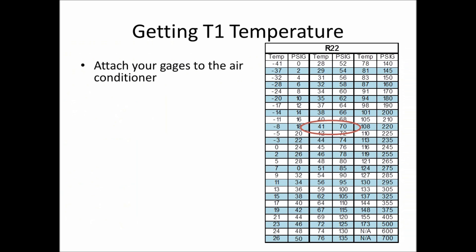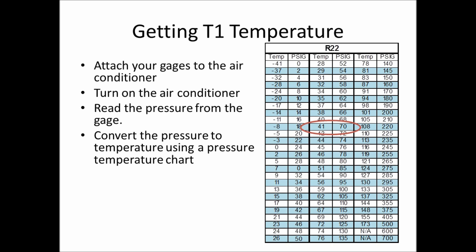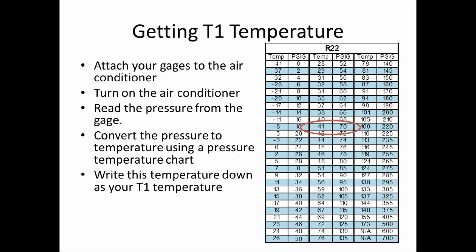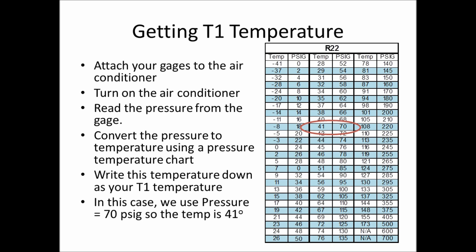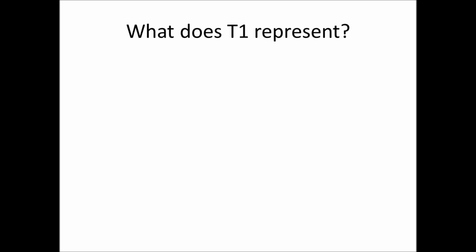Getting T1 is fairly easy. You attach your gauges to the air conditioner, make sure it's on, running, and has settled down. You read the pressure from your low pressure gauge and convert that on your pressure-temperature chart. In this example we're looking at 70 psig, which represents a temperature of 41 degrees — that's your T1 temperature.